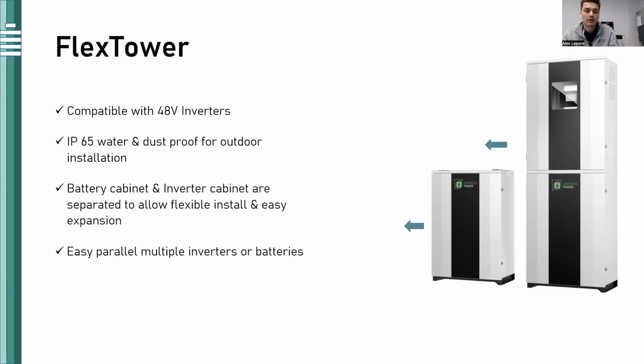A word of caution - sizing and designing, I'm going to say it again, very, very important. Talk to the manufacturer, talk to a couple manufacturers maybe. Small batteries on large inverters cause problems. If we had our NV 12 kilowatt inverter with one E-flex, that's a really big inverter charging a very small battery - that's not going to be good for the battery. You're going to be putting way too many amps in at one time, and it's going to affect the battery's lifespan negatively, versus if we sized it with maybe two or three of the E-flexes. So we have sizing and designing webinars, a lot of training on our website, and forms you can review. Proper sizing and designing goes a very long way for the investment in your energy storage system.